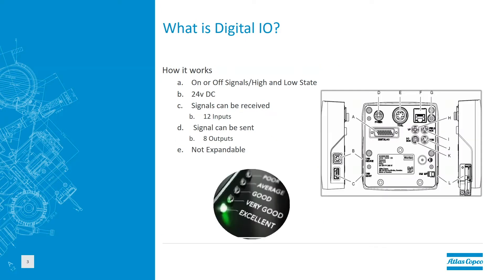So how does digital I/O work? Basically, digital I/O sends an on or off signal, or a high and low state. This is provided through 24 volts DC. There are up to 12 input signals that can be received on the MTF-6000, and it also can send out a maximum of eight outputs. These are not expandable. How to wire these can be found in the configuration manual for the MTF-6000 or in the ToolsTalk MT manual.